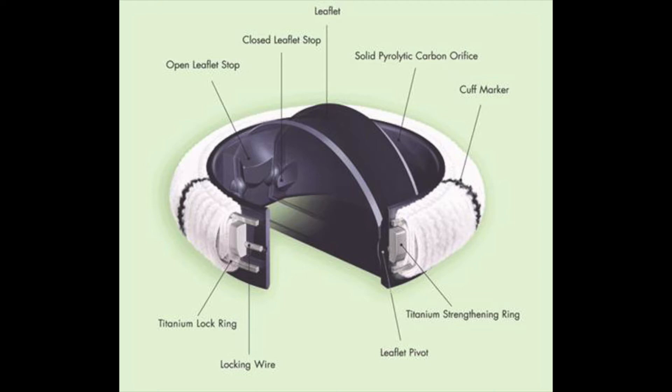The titanium is usually created by an outside manufacturer and made from machined bar stock. The polyester comes in the form of tubes and is usually deburred by the supplier and/or valve manufacturer. However, potentially the most important part of creating an artificial heart valve is the process of creating the pyrolytic carbon that coats the bi-leaflets and forms the inner ring. This process is referred to as a fluidized bed process.